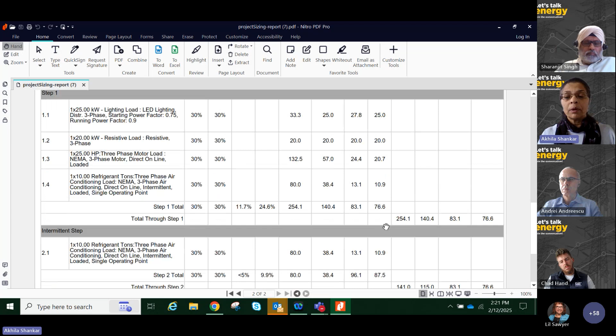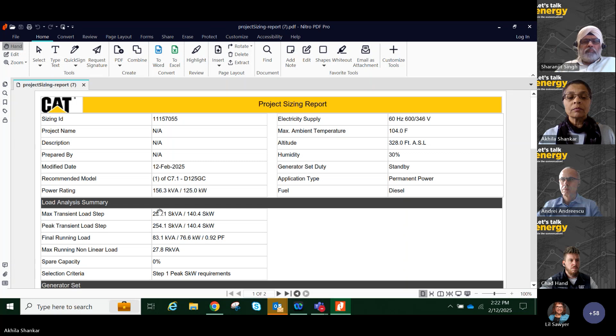Here you will also see that the sum total of the running load is about 76 kilowatts, which is around 61% of the 125 kilowatt rated generator that was recommended.